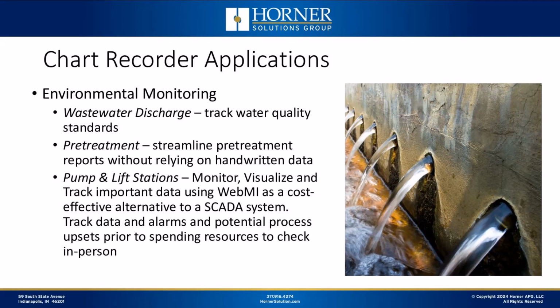And then, of course, environmental monitoring is an application where it's very valuable. So there are plenty of manufacturers who, for instance, are discharging water into either a body of water or maybe a municipal water system. And there are regulatory requirements, water quality metrics that have to be measured and logged, and reports that have to be submitted, those sorts of things. And having a device like this makes that very straightforward. Okay, so the reports that need to be generated on a regular basis can be based off real recorded timestamp data and not handwritten notes, for instance.